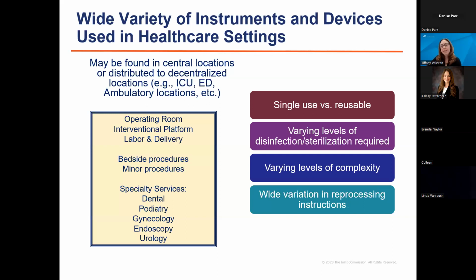A lot of our instruments and devices have varying levels of complexity. Think about simple stainless steel surgical instruments versus these crazy big sets of orthopedic instruments, right? If you've ever seen a hip replacement and you see that thing that looks like a cheese grater on the end of a stick, right? Those things are really, really hard to clean. And there's a wide variation in reprocessing instructions. So think about in your dental settings, if you have them, that's like the number one place where if you have a dental setting and they have dental handpieces, which they probably do, there could be 10 different dental handpieces and they could have 7 different instructions for sterilization.